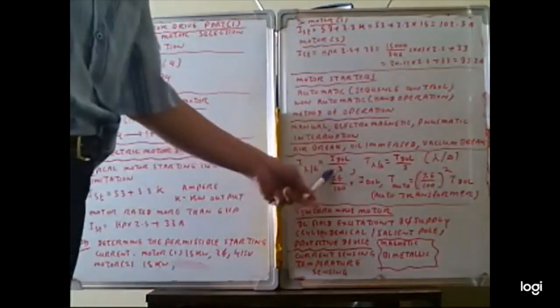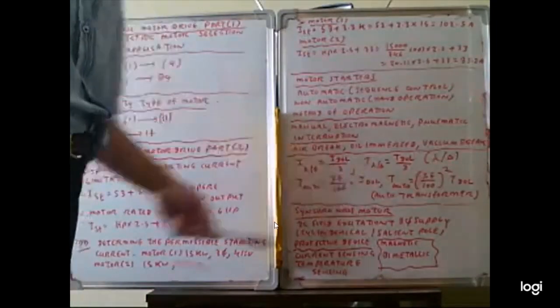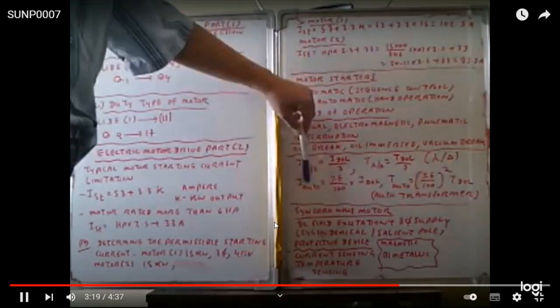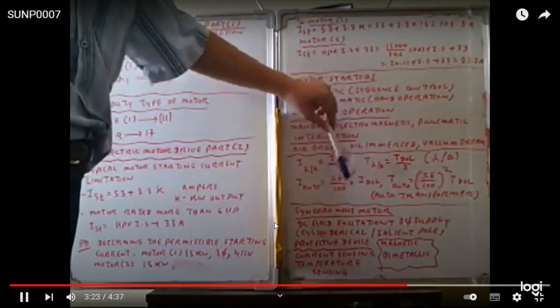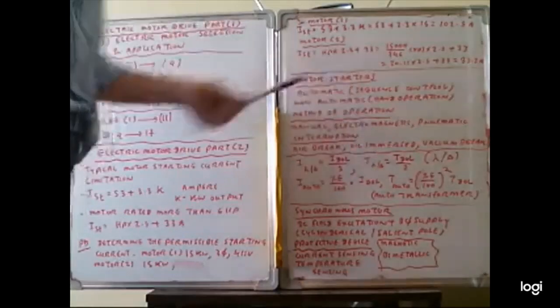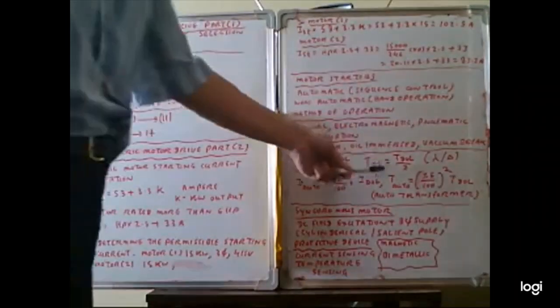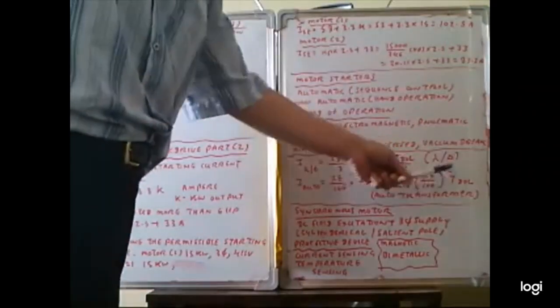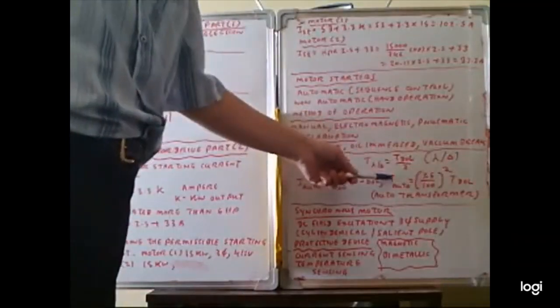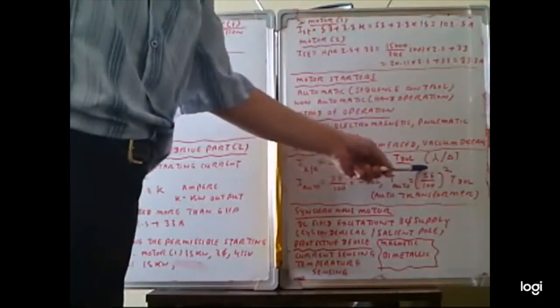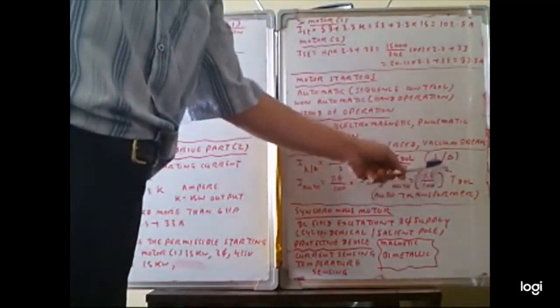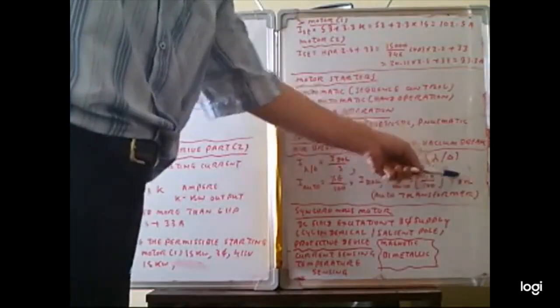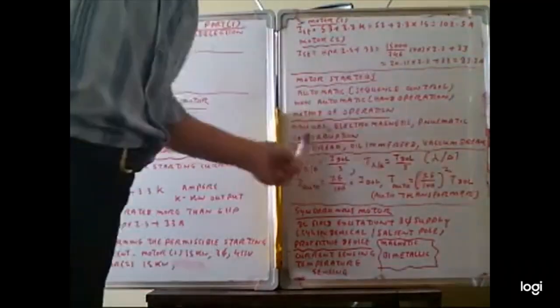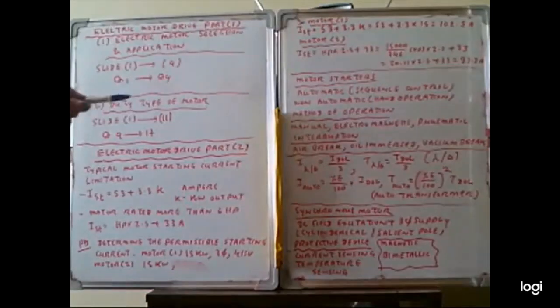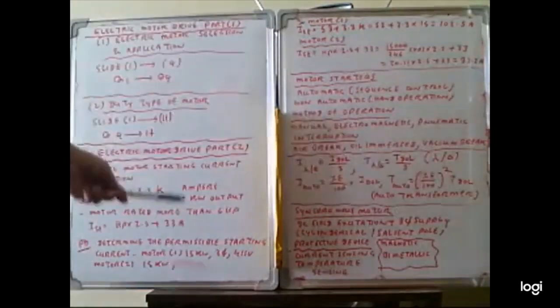I_auto is equal to percentage E by 100 times I_DOL. This means the starting current of the auto transformer starter is equal to the percentage voltage divided by 100 times the starting current of the direct online starter. T_auto is equal to (percentage E by 100) squared times T_DOL. So the starting torque of the auto transformer starter is equal to the percentage voltage by 100, squared, times the starting torque of the direct online starter. So this is the torque and voltage equation for the star-delta and the auto transformer starter.